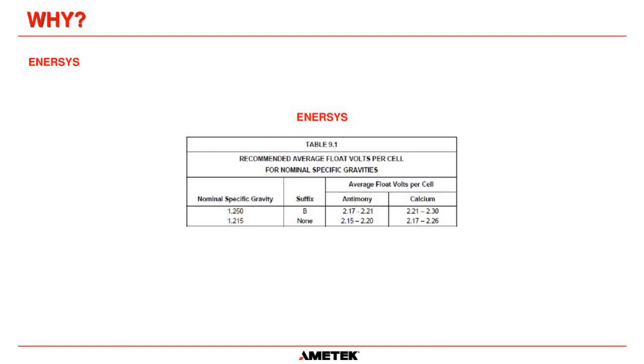And that's basically the nominal specific gravity is higher on this one here because they have more sulfuric acid in the electrolyte solution than they do on this one here. So this one here will actually give you more power than this one here, okay? But that changes what the system needs to be charged at.